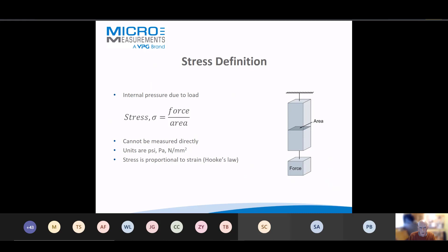It's defined with the Greek letter sigma as force divided by area. You cannot put a pressure transducer into a solid, so you can't measure that pressure directly. You'll talk about units of pascals or pounds per square inch. You can calculate the stress because stress is proportional to strain via Hooke's law, which many of you would have done at school, college or university. So we measure strain, and we can then calculate the stress if we know the material properties. We have a strain gauge measuring strain, and we use that to calibrate in whatever units we wish.